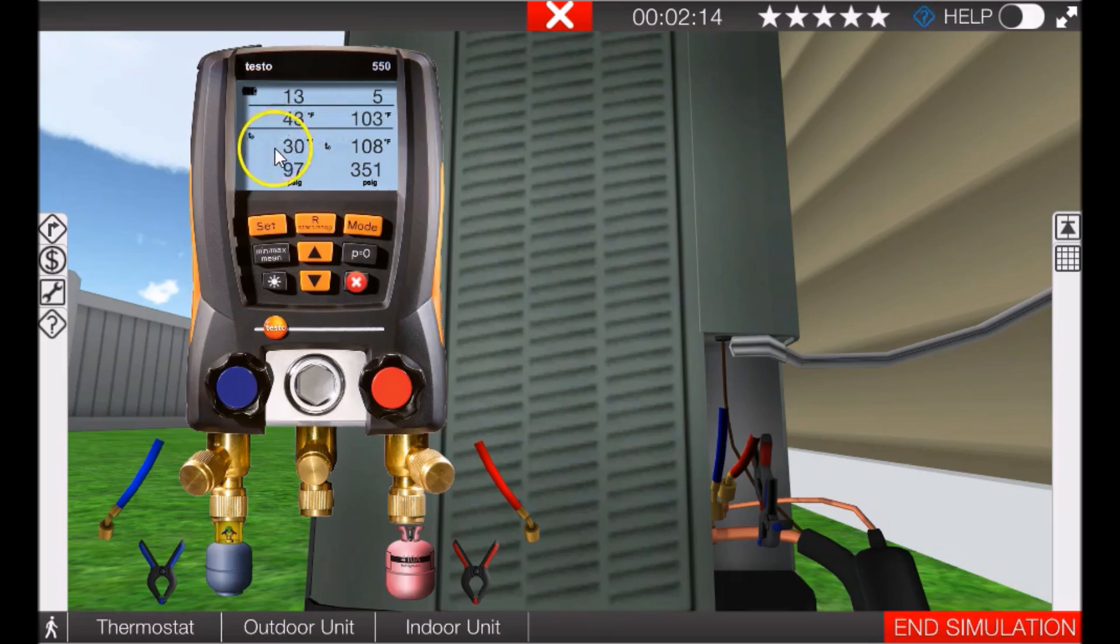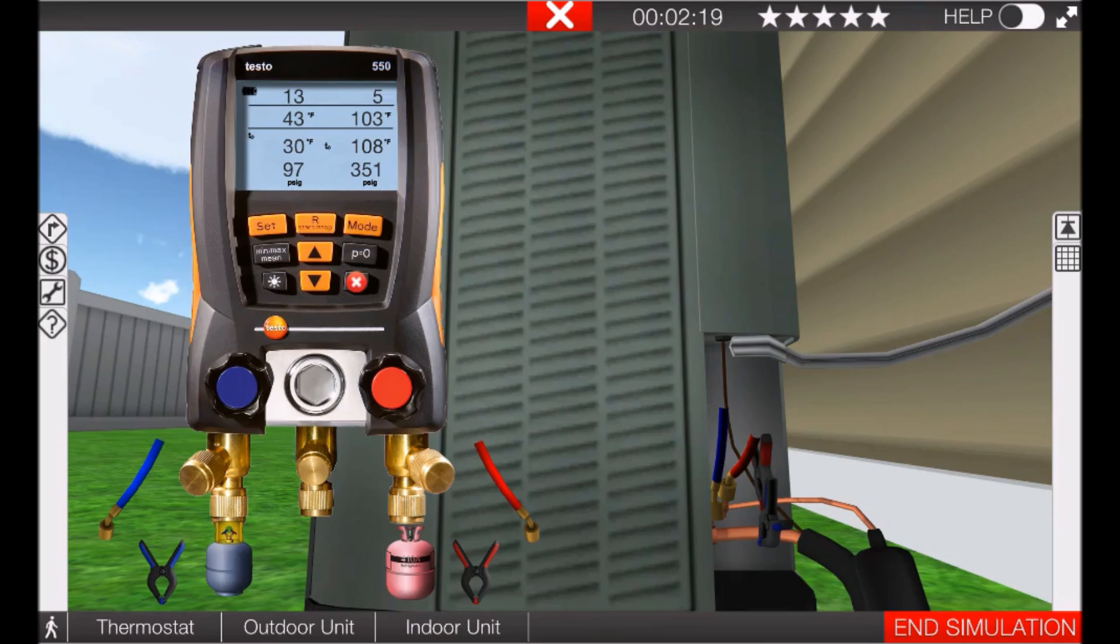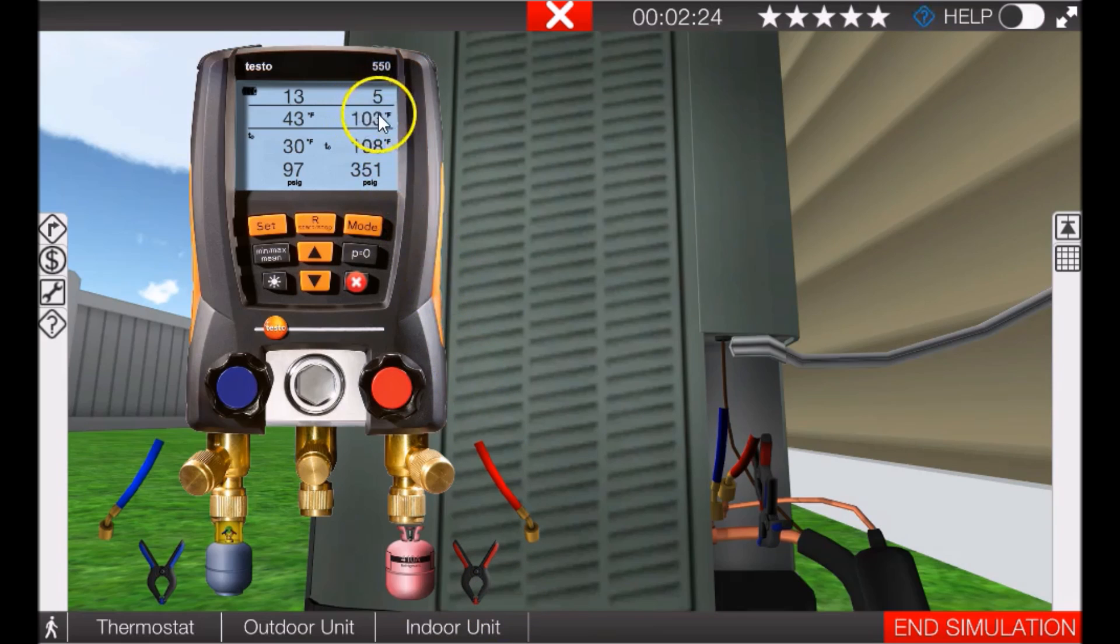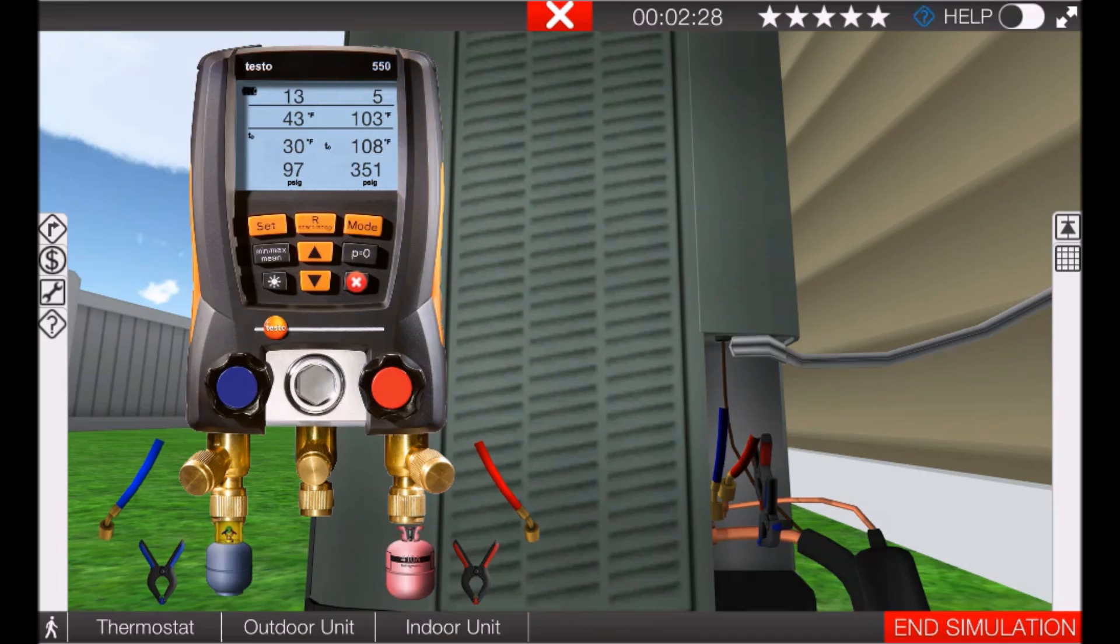But if you'll notice, this 30 degree saturation point on the suction side indicates that the coil is going to begin to freeze because it is below freezing. We do have 5 degrees of subcooling, so we know we have a system that's charged properly.